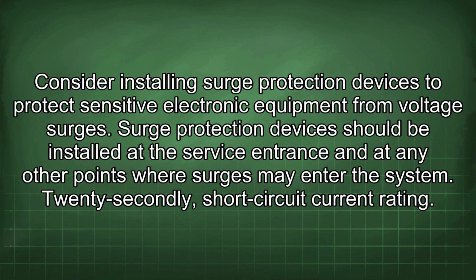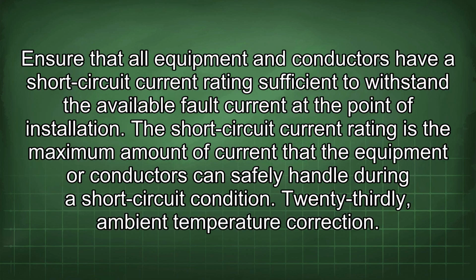Consider installing surge protection devices to protect sensitive electronic equipment from voltage surges. Surge protection devices should be installed at the service entrance and at any other points where surges may enter the system. 22nd, short circuit current rating. Ensure that all equipment and conductors have a short circuit current rating sufficient to withstand the available fault current at the point of installation. The short circuit current rating is the maximum amount of current that the equipment or conductors can safely handle during a short circuit condition.